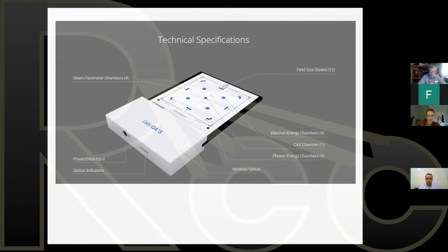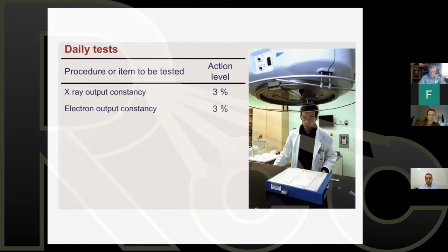This device gives assurances that the field size is correct, the flatness and thus the energy is correct, the symmetry of the beam, is the beam properly steered, that's correct. And finally, the output, is the output correct? Here is another device, does the same thing, being set up by a therapist or a physicist. Notice the small water tank in the background here. This is a small 1D tank. Small 1D tank with a hand crank on it. Actually, it's not even a servo controlled tank. This is the old fashioned one with the hand crank on it, and it still works fine.